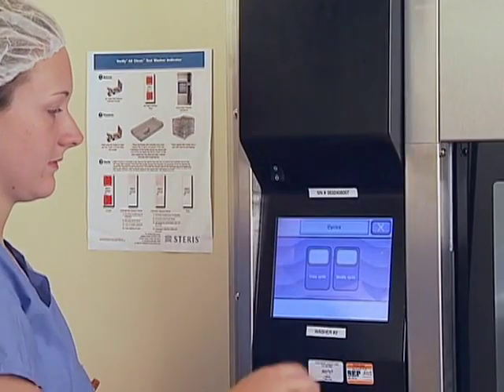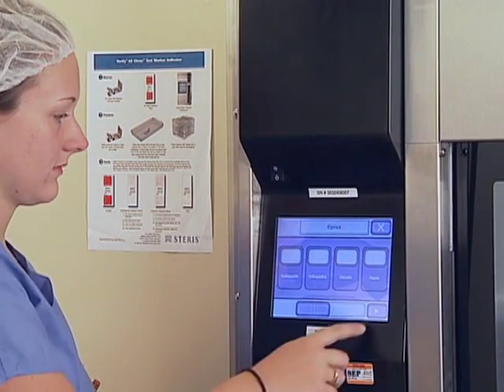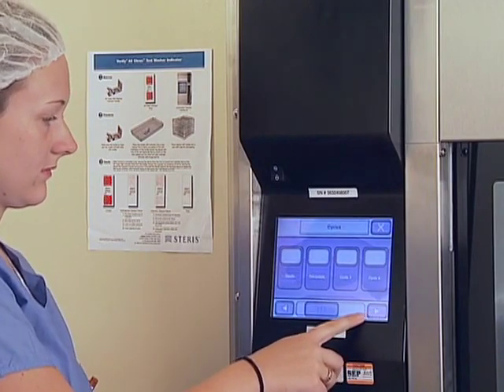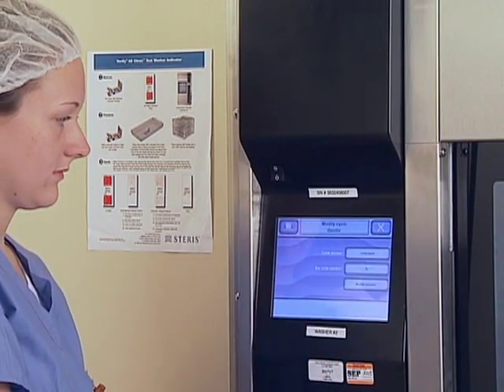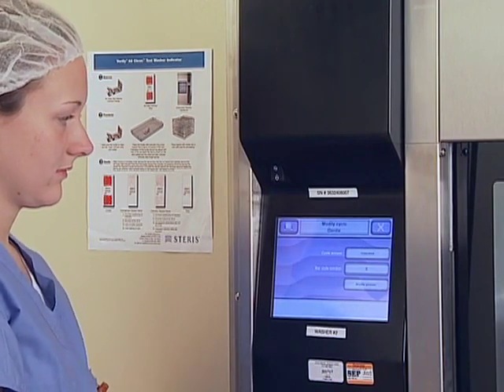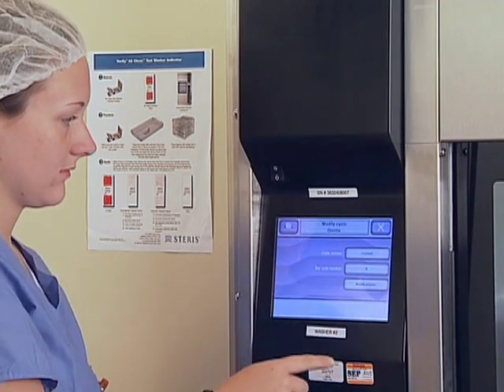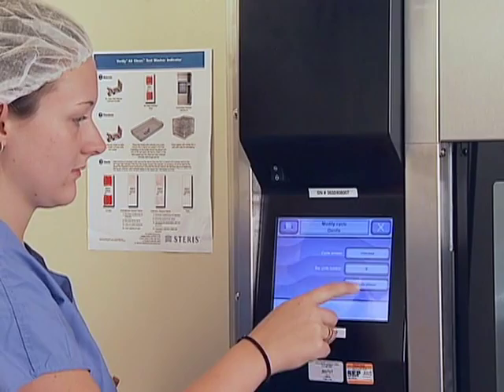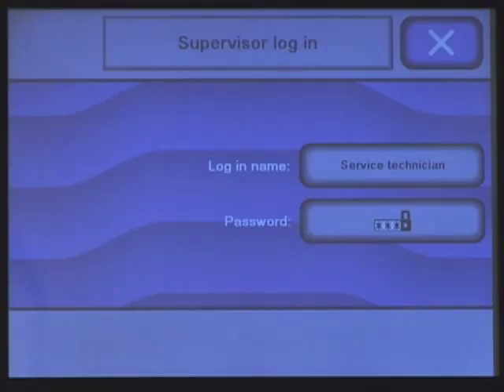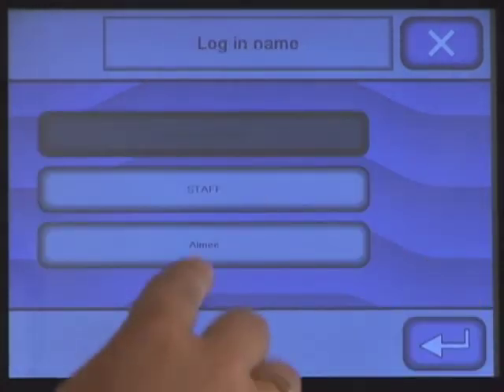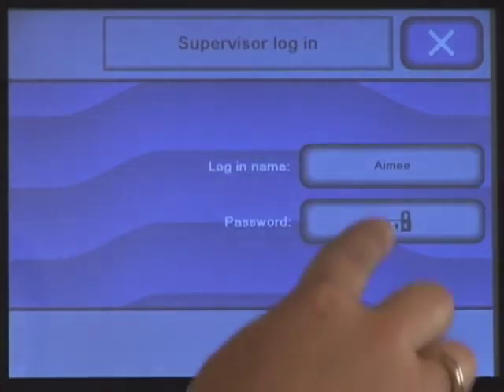As mentioned earlier, this washer comes with a set of pre-programmed cycles. Each phase within a cycle has its own parameters which can be modified to better accommodate your department's processing needs. Customized cycles can also be added. Only a supervisor can modify a pre-programmed cycle or add a new one. Start by logging in to the supervisor screen. Select the appropriate supervisor login name, and then press Enter.